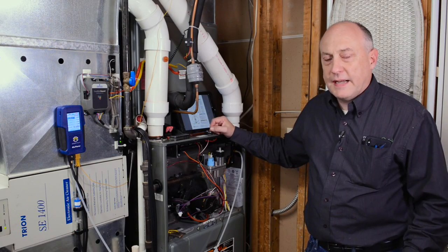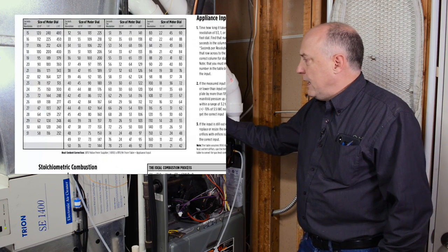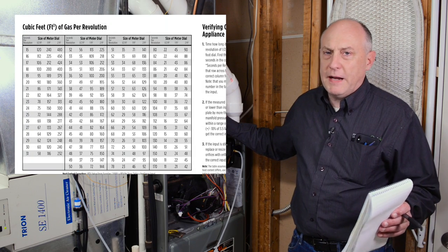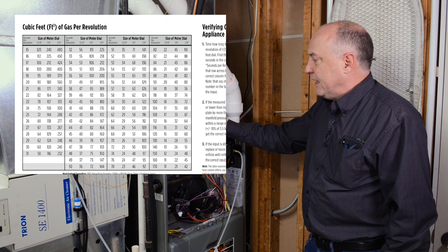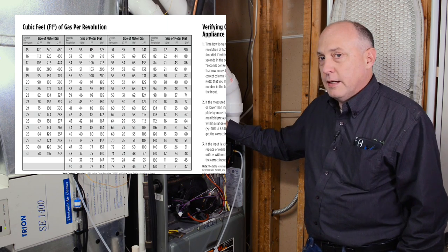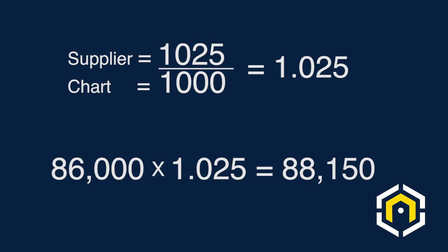The meter clocked at 42 seconds. On the last page of the combustion guide is a gas meter clocking chart. A great part about having this on your iPad is you can zoom in on the reference material right at your fingertips. At 42 seconds on the chart, I'm at exactly 86,000 BTUs of input. But this chart is rated for 1,000 BTU gas, so we have to make some corrections. I called my gas supplier and found out my heat content — here in Ohio we're at 1,025 BTUs per cubic foot. So I take 1,025 divided by 1,000, which gives a 1.025 multiplier. I take 86,000 times 1.025, and my actual input is 88,150 BTUs. Pretty spot on for a 90,000 BTU furnace.